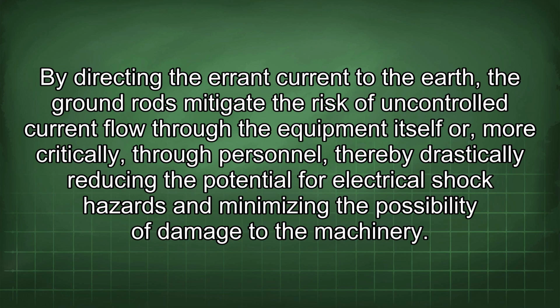By directing the errant current to the earth, the ground rods mitigate the risk of uncontrolled current flow through the equipment itself or, more critically, through personnel, thereby drastically reducing the potential for electrical shock hazards and minimizing the possibility of damage to the machinery.